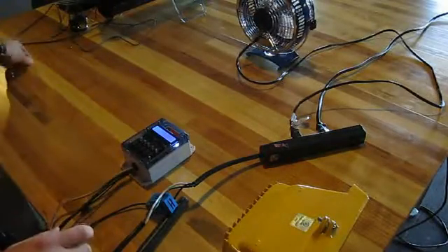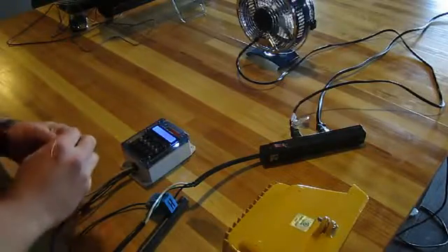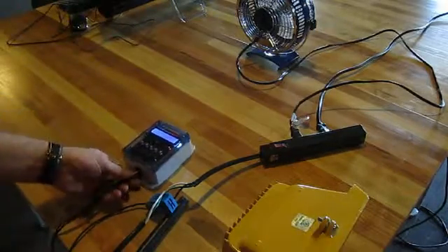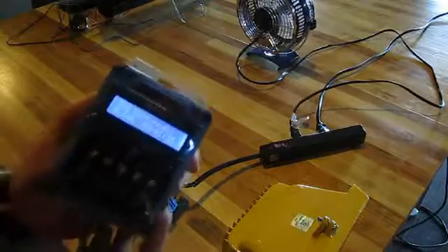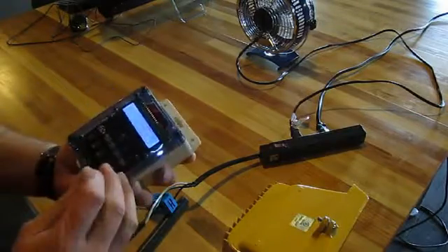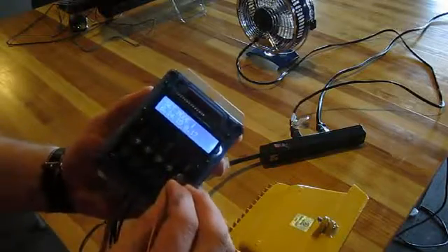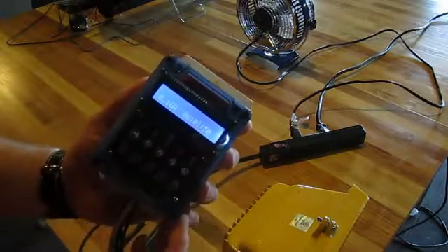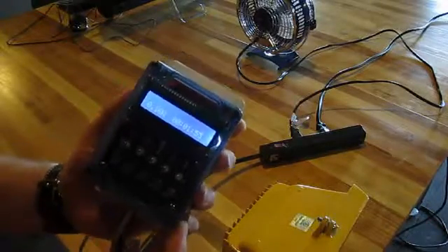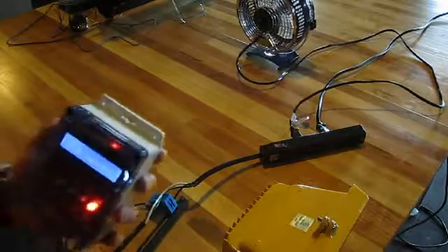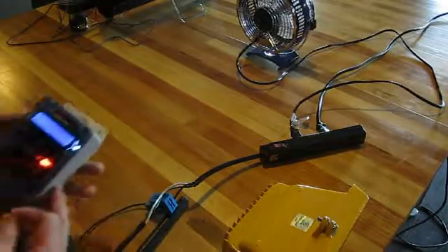So, with everything at 0, what we will do is set the fan on low, and you'll see that you've got some small amount of current that it's reading there, and we will assign this first button to be the fan on low. So we've got fan L. There's a little delay there to buffer for large motors starting and so on.